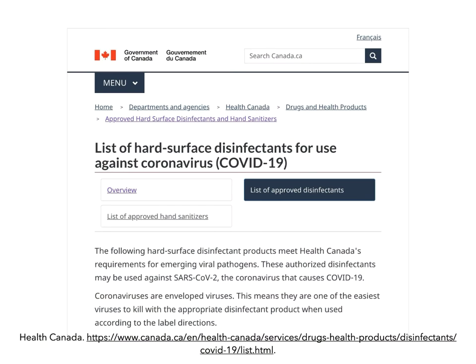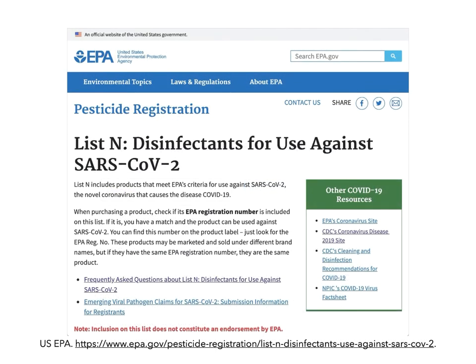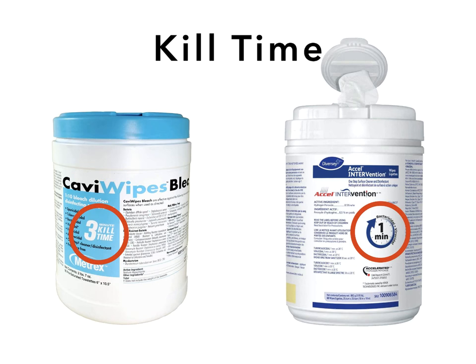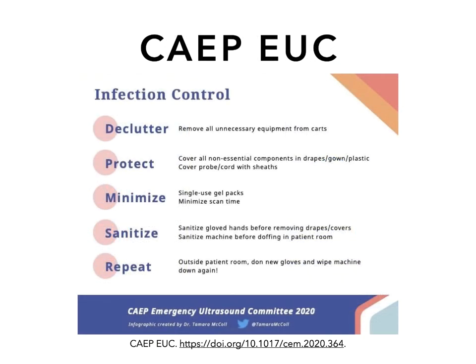Once you've completed your scan, clean your gloved hands with hand sanitizer, then remove any cover you have on your machine — taking care not to disperse viral contaminant — and wipe it down with an appropriate disinfectant. Health Canada maintains a list of disinfectants that are effective against COVID, as does the United States Environmental Protection Agency. Most ultrasound manufacturers are waiving rules about machine-specific disinfectants and will support the use of any product effective against COVID. Pay attention to your product's kill time — the amount of wet time your disinfectant needs to be on the machine surfaces to be adequately effective.